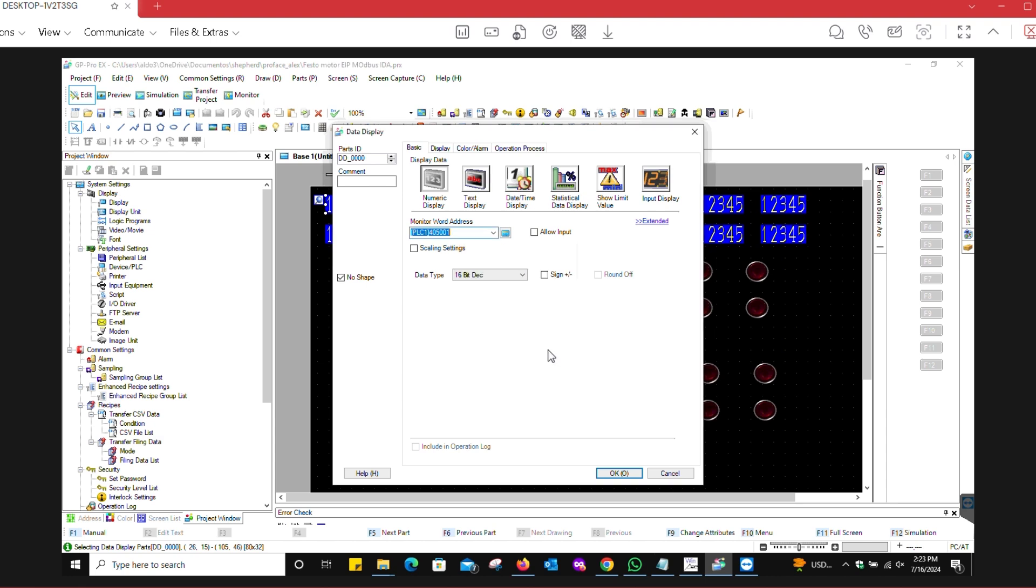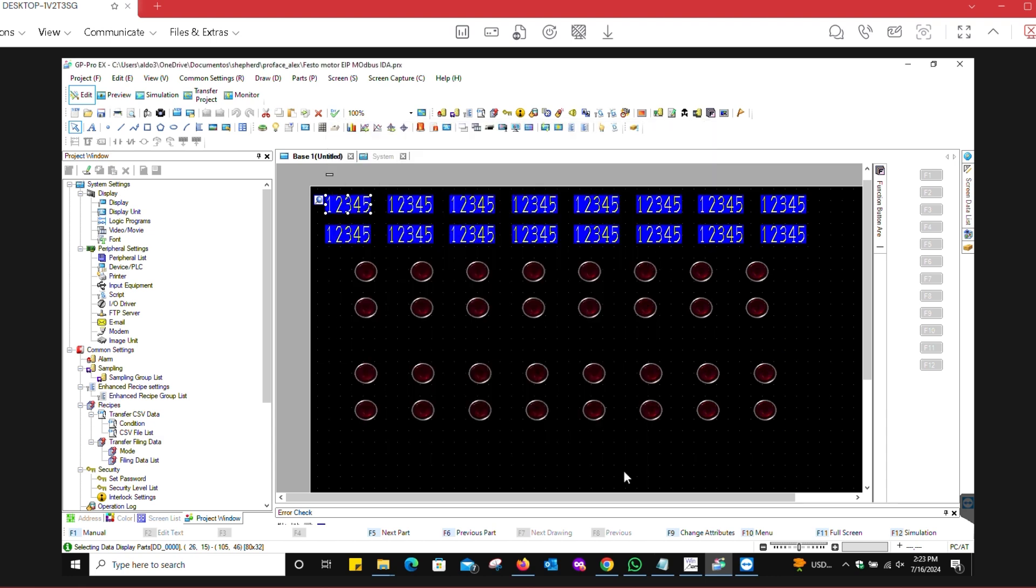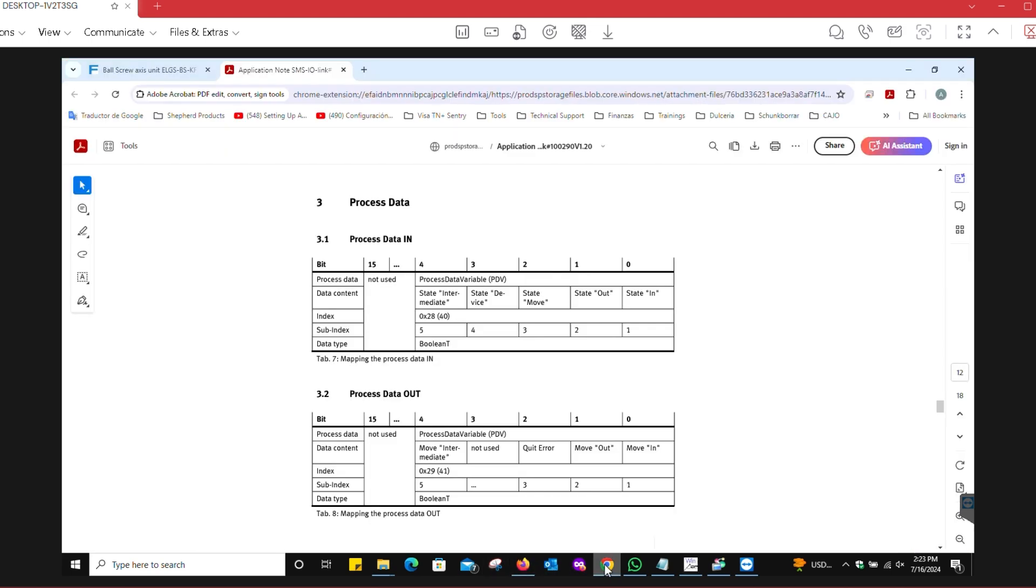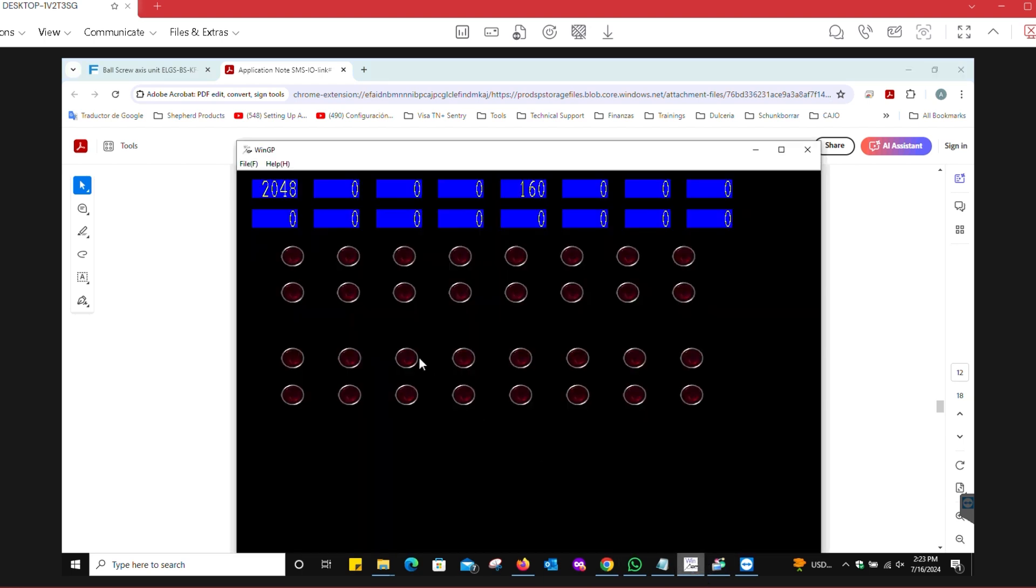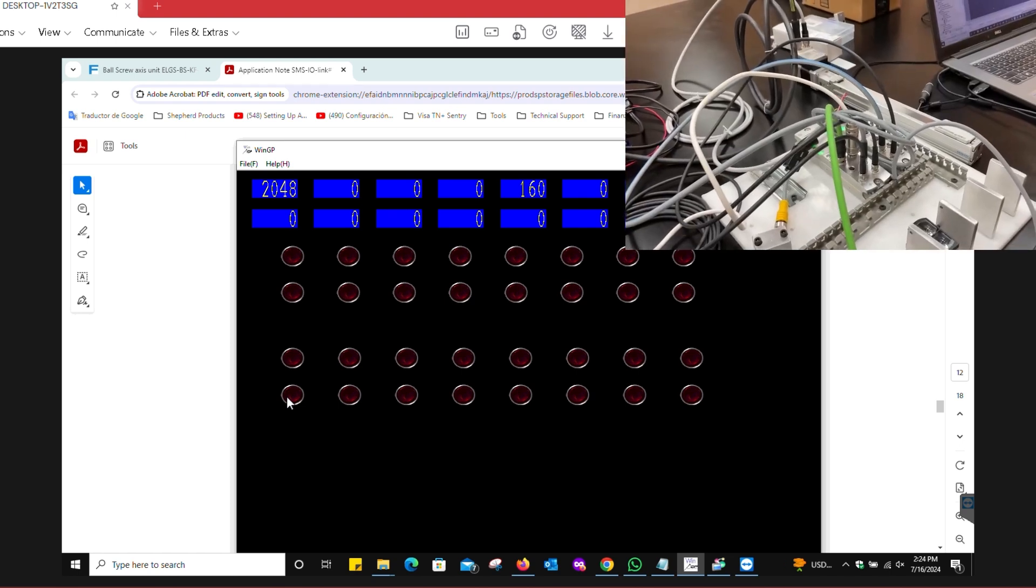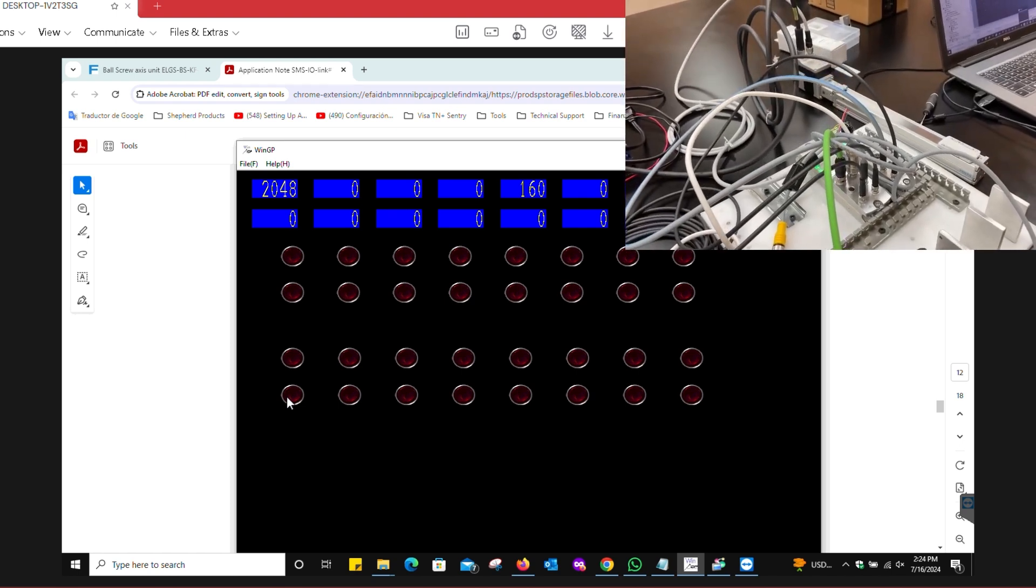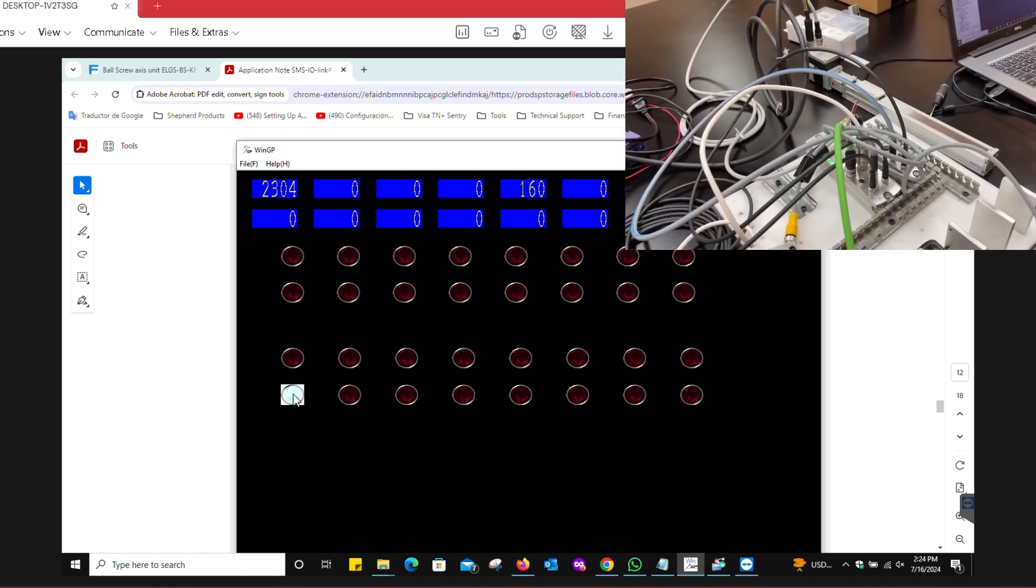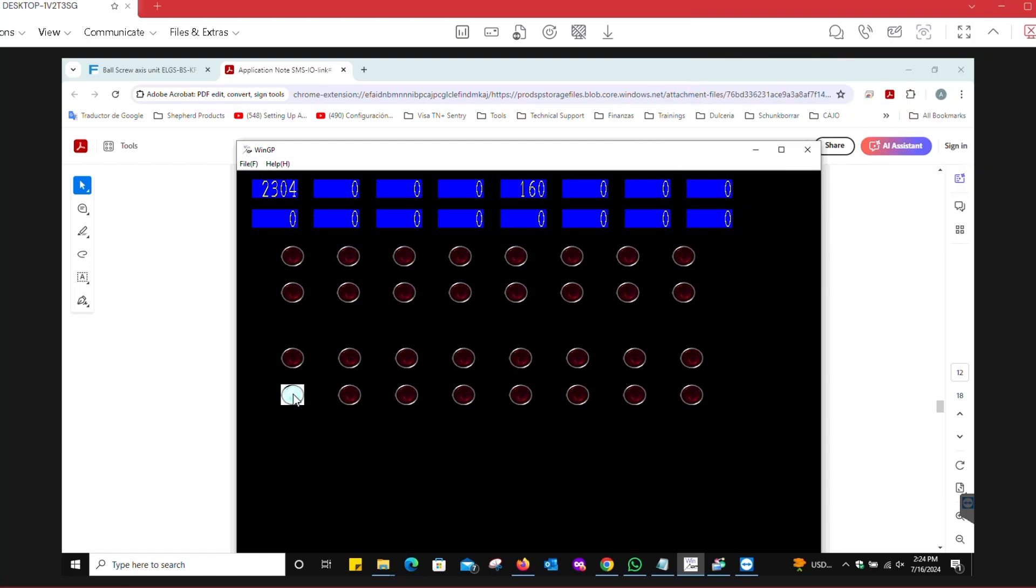If we go into the simulation, you're going to see here that we're getting some data. If we wanted to move in and move out this actuator, we would look at the process data out. If I wanted to move in, I have to turn on bit zero. Remember that the bytes are swapped here, so this is bit zero, this is bit eight. Now I can physically see that the actuator moved in.